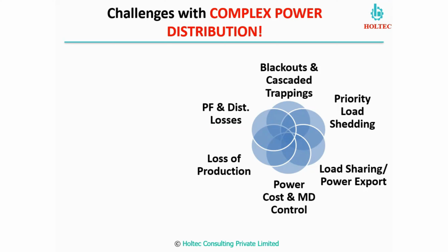In the same way, suppose we are doing the export, say we have to export 5 megawatts, but because of these fluctuations, sometimes it is not possible to fix 5 megawatts firmly on the grid side. We cannot give the set point for the power export and control our source power drawn. So this is not actually possible with this complex power distribution.